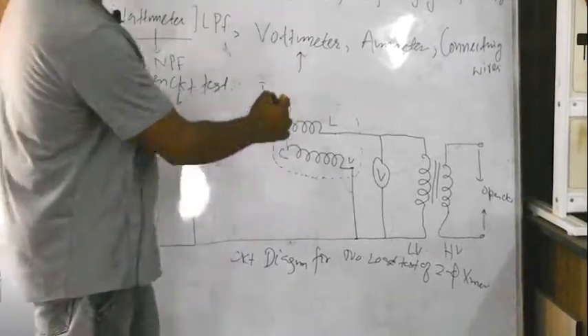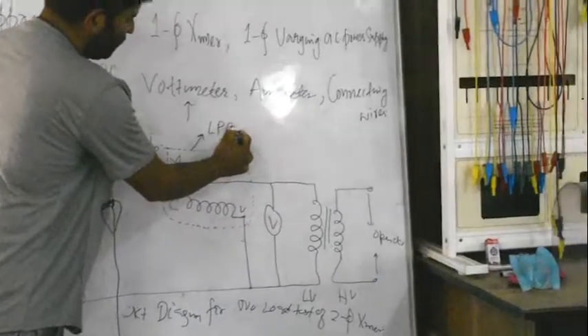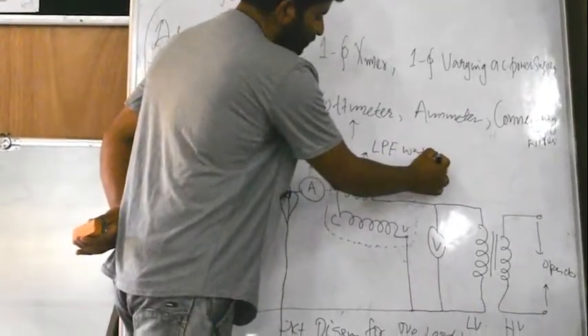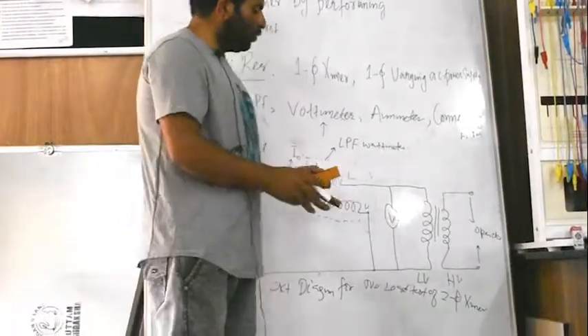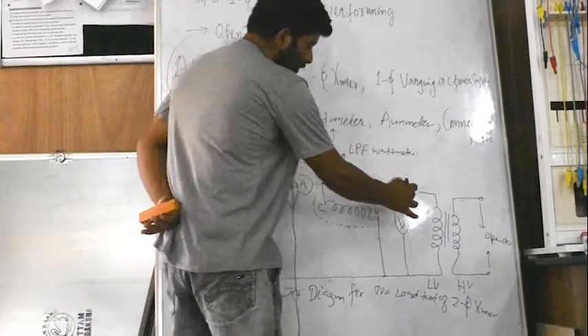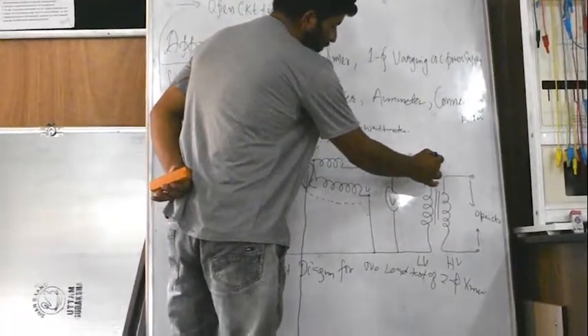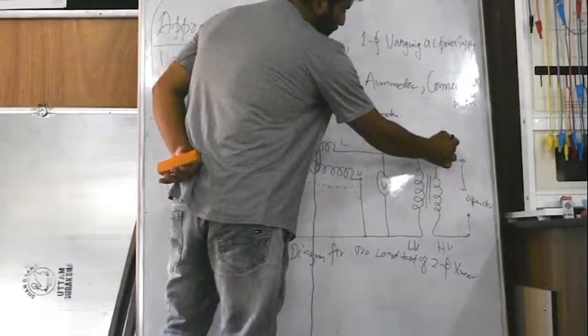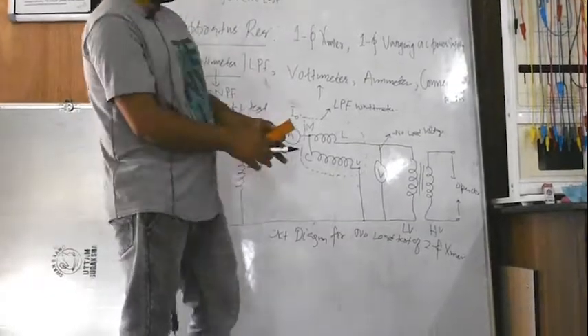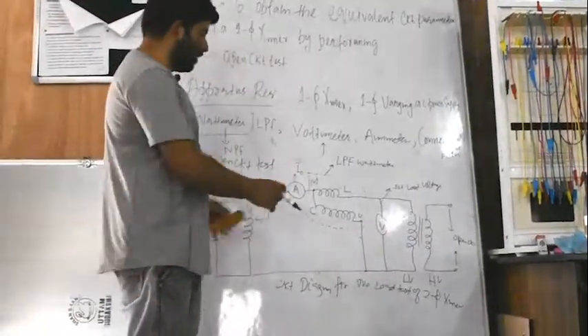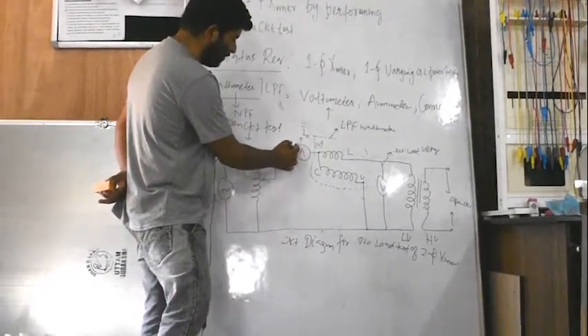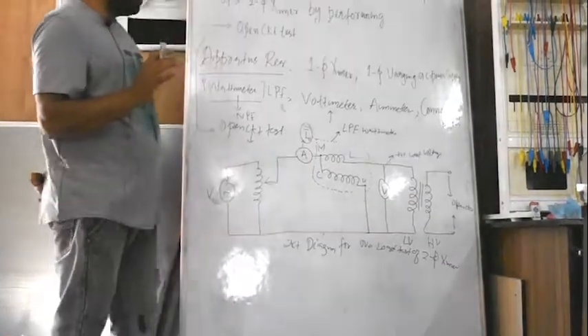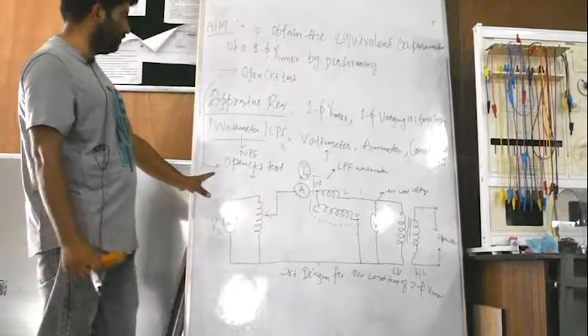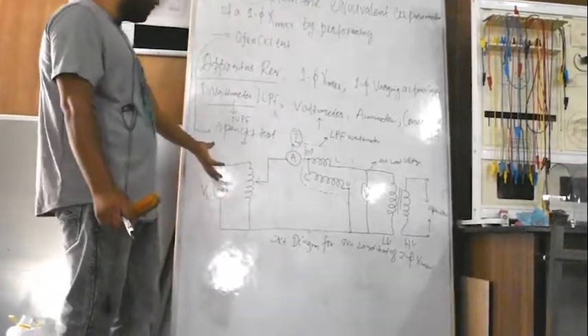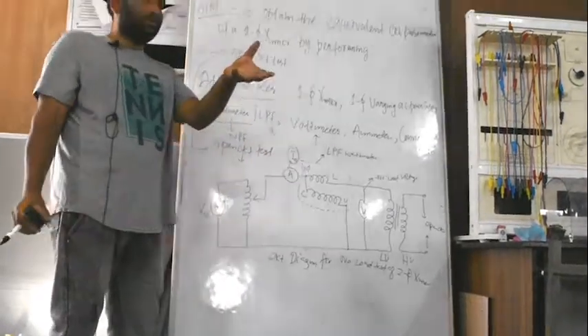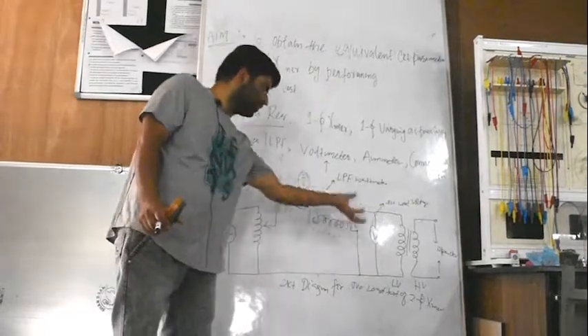This is the wattmeter, so this will be a low power factor wattmeter, LPF. This is the voltmeter connected across the winding which is energized. This will measure the no load voltage or the rated voltage. Depending upon the current which the winding will take at no load, it will be recorded by this ammeter. So this I naught will be the no load current. So the basic operation will start like this. We will connect a varying AC power supply, which may feed the rated voltage upon which our transformer is operating.